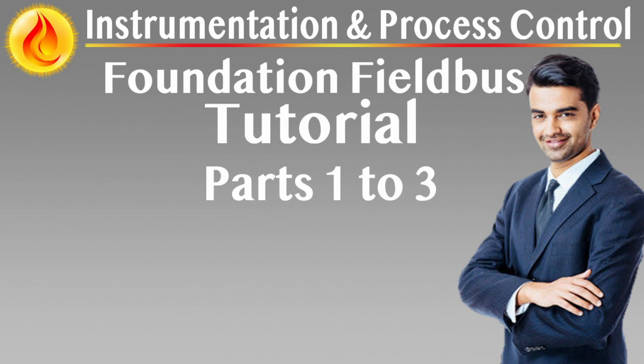All devices must support local and remote configuration using standard engineering tools such as Field Device Tool (FDT), Device Type Manager (DTM), or host DCS configuration suites. Basic configuration must also be accessible via handheld configurators using the Fieldbus protocol stack. Field calibration, zero span adjustment, and mode switching, manual, auto, out of service, must be supported through the digital interface.